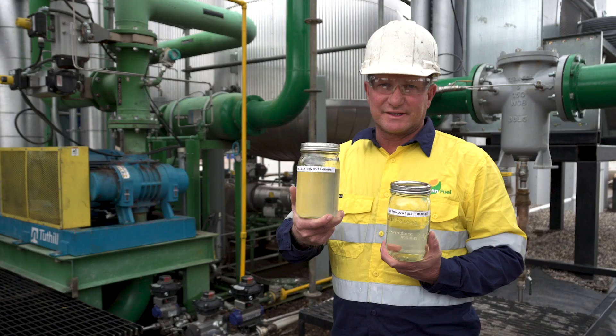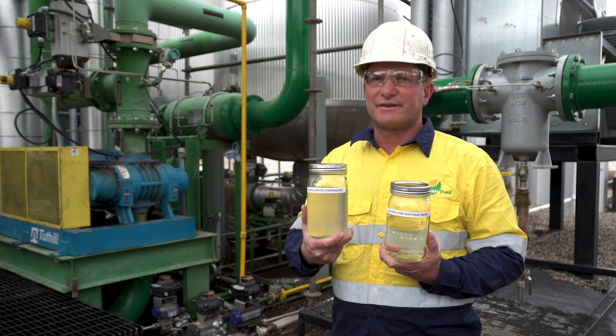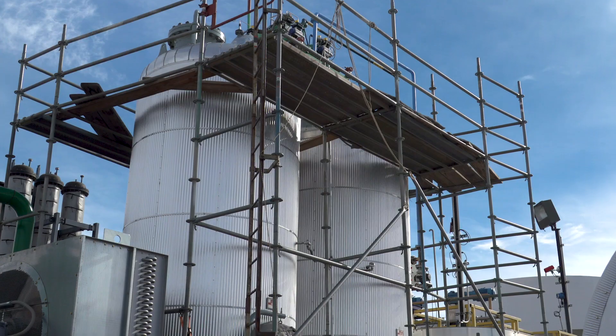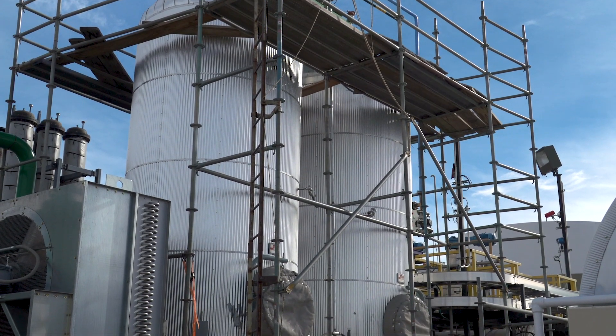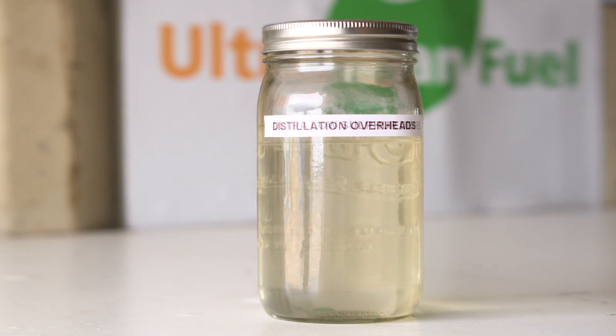When the diesel passes through the distillation column, the diesel that comes over the top passes through our absorbent towers, which you can see in the background here, and it comes out at less than 10 parts per million from the original 130 parts per million.